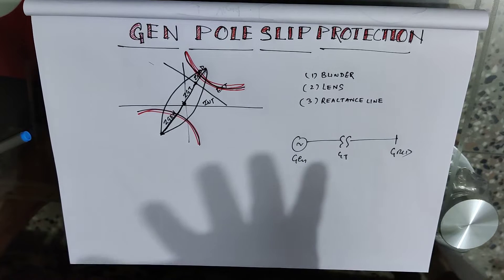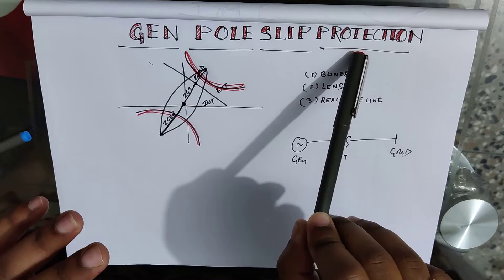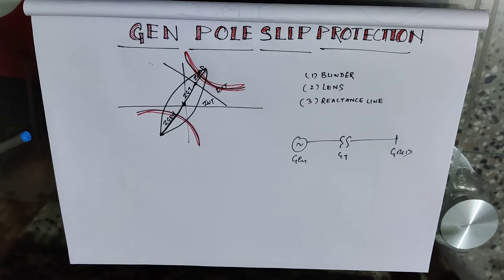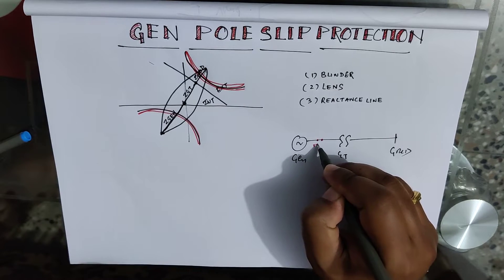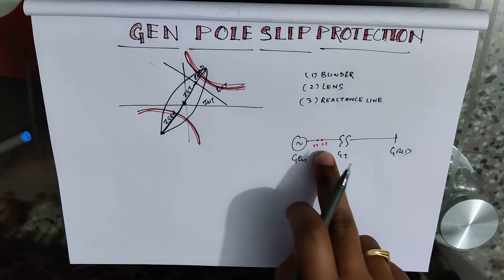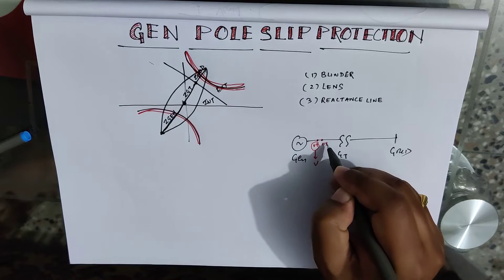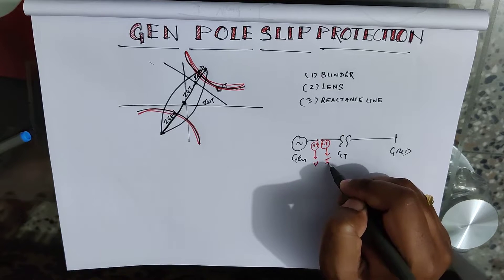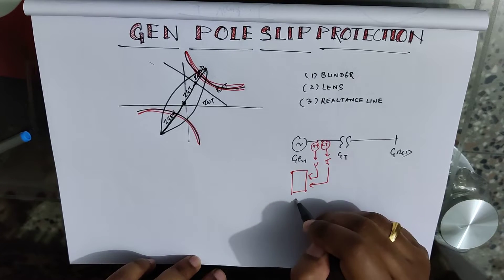To prevent that dangerous blackout condition, this pole slip protection is present in the protection relay of the generator. The voltage transformer and current transformer at the terminal of the generator send voltage and current into the protection relay device.